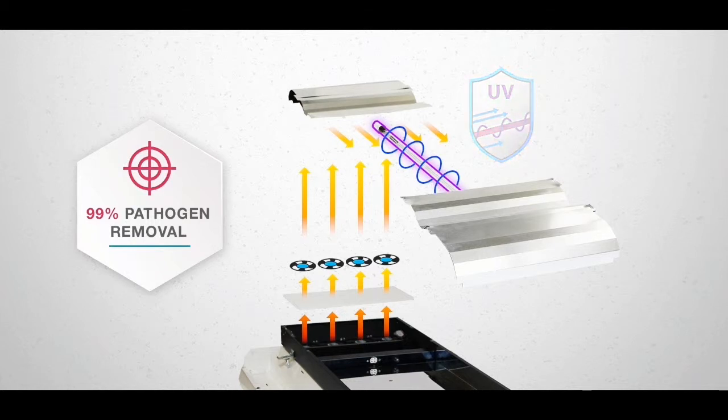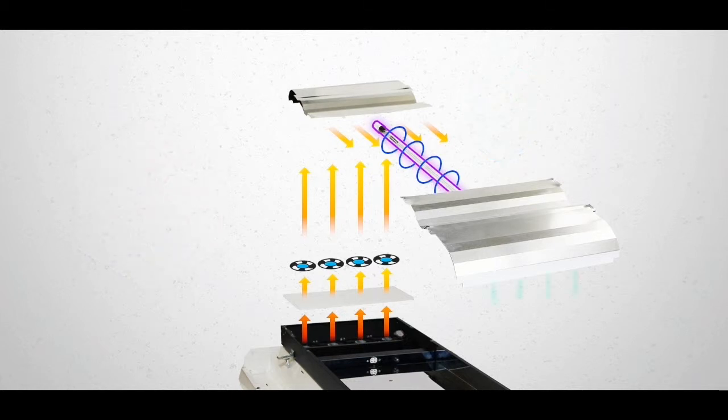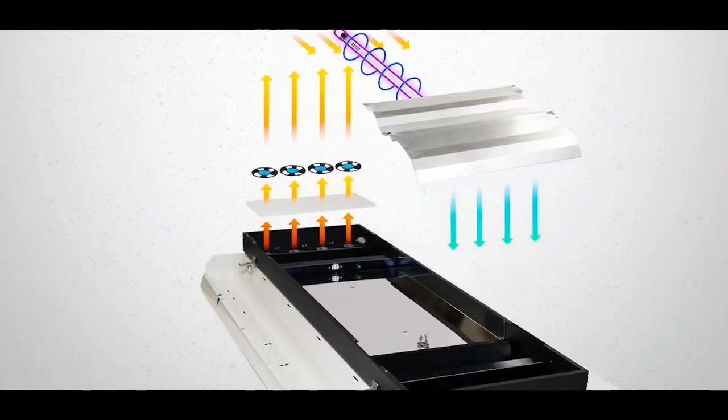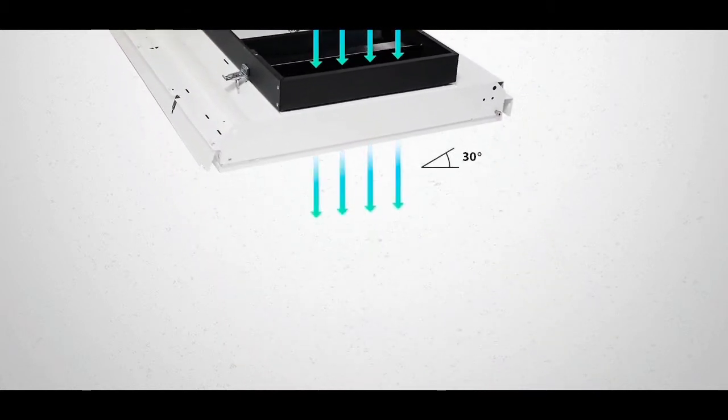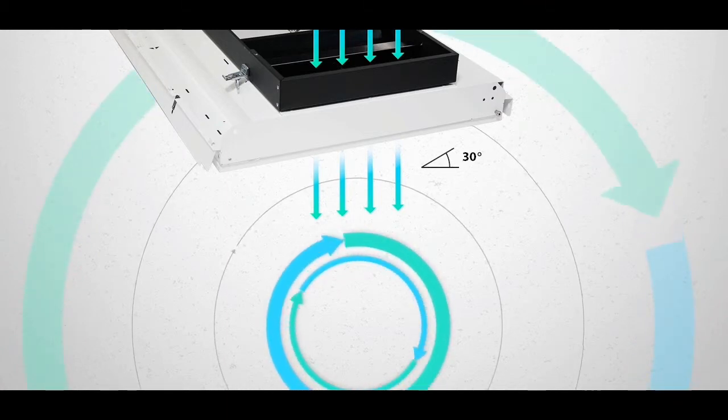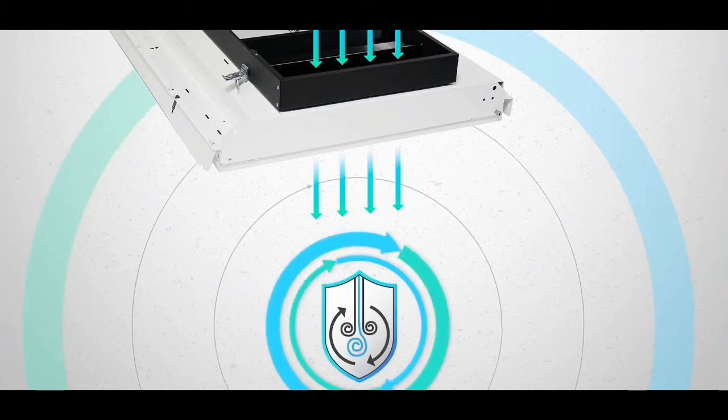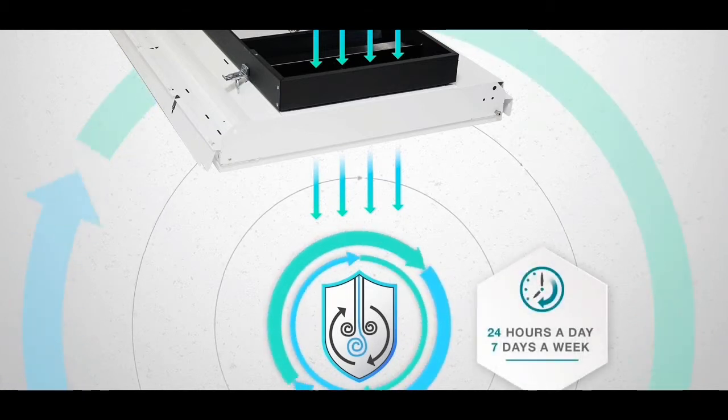The purified air is then returned to the space through an additional set of safety baffles and out the opposing grill which has a 30 degree angle on the blades to force air throughout the room. The CDC recommends dilution as the fourth line of defense and our device operates 24 hours per day constantly changing and purifying the air. In a 10 by 10 room we will change the air an average of four times per hour.